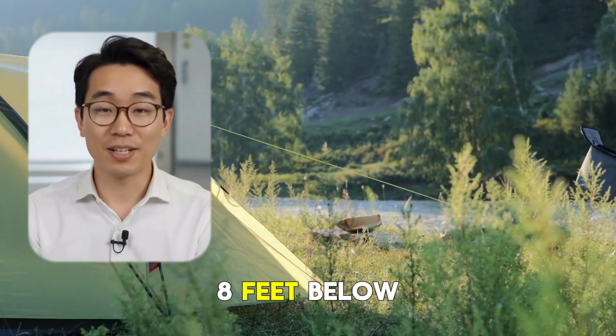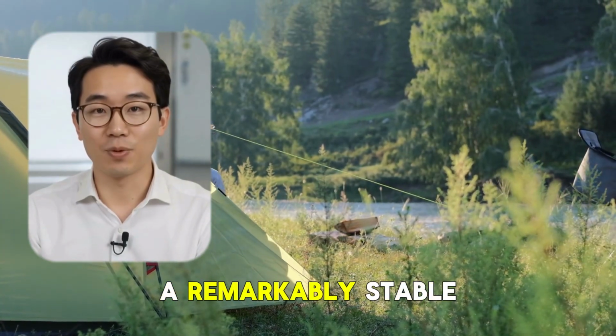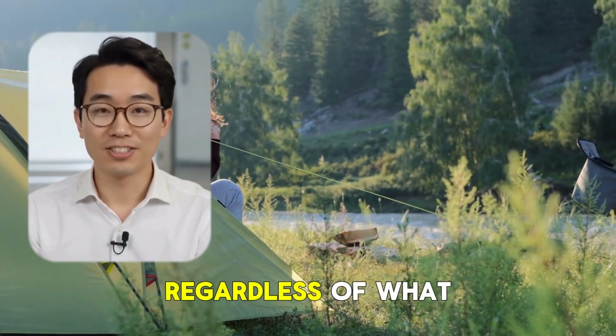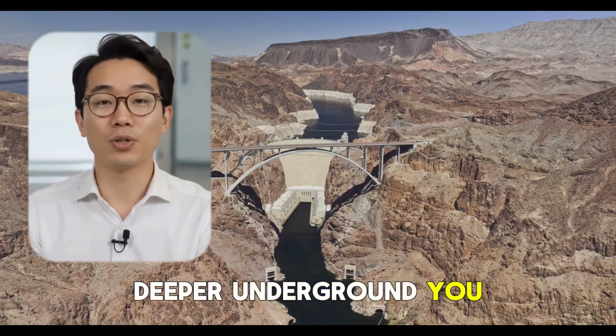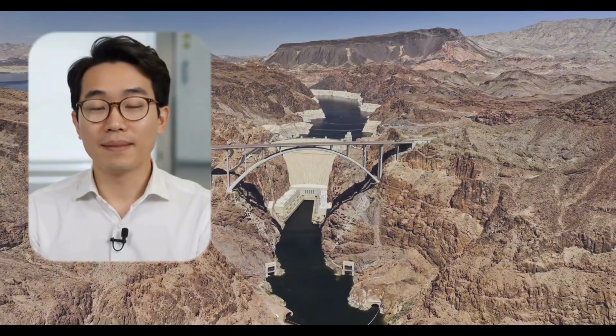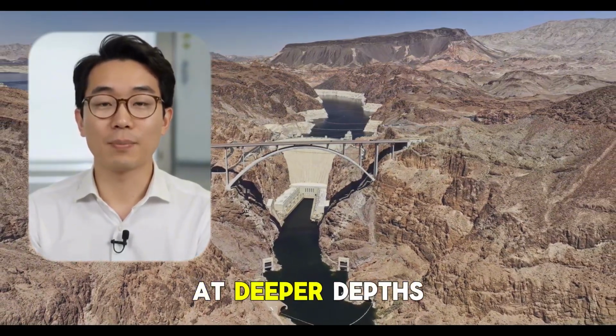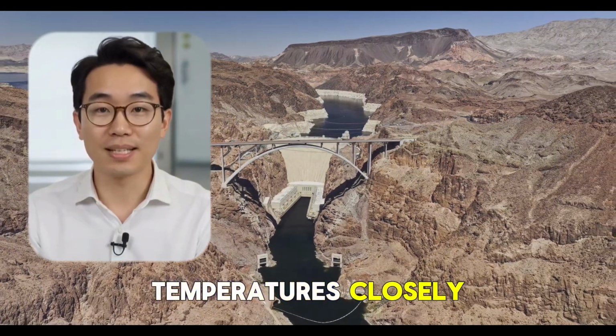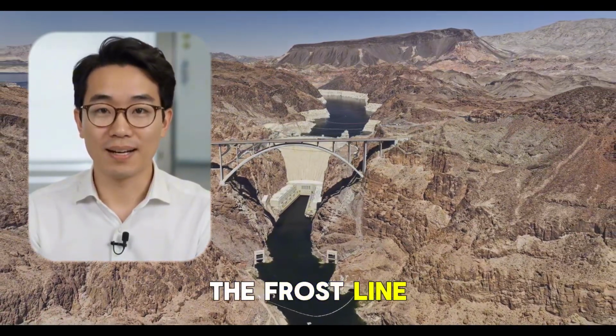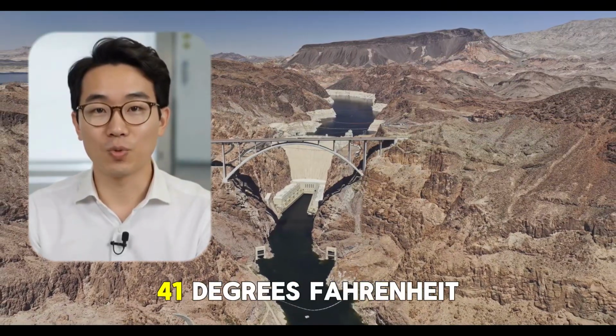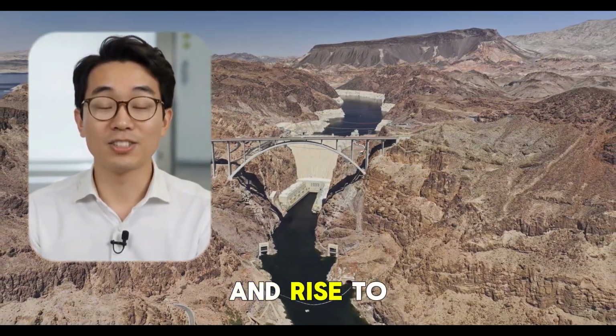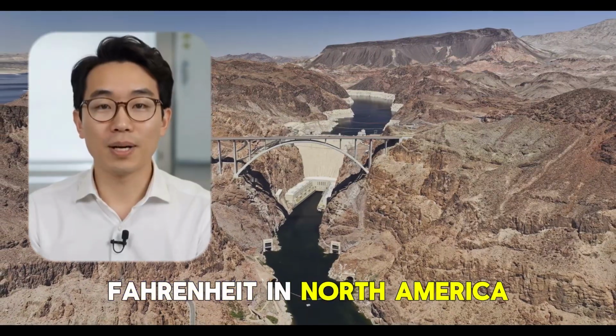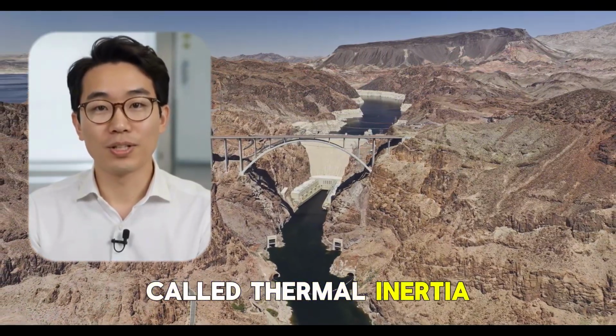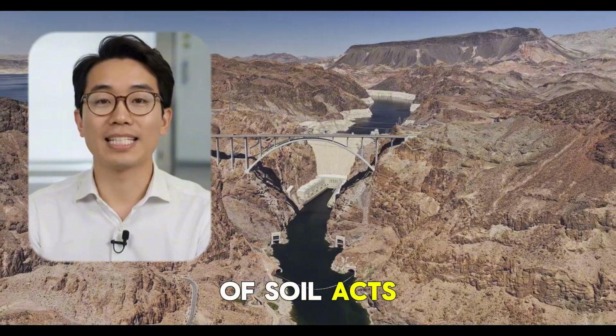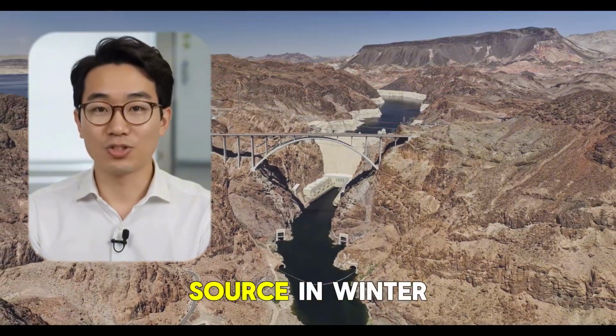At 6 to 8 feet below the surface, the earth maintains a remarkably stable temperature, regardless of what is happening in the atmosphere above. Generally speaking, the deeper underground you go, the more stable the temperature. The air moving through the tubes in the earth at deeper depths will follow those temperatures closely. Ambient temperature below the frost line at an 8-foot depth may drop to 41 degrees Fahrenheit in winter and rise to around 65 degrees Fahrenheit in North America. This phenomenon is called thermal inertia. The massive volume of soil acts as a heat sink in summer and a heat source in winter.